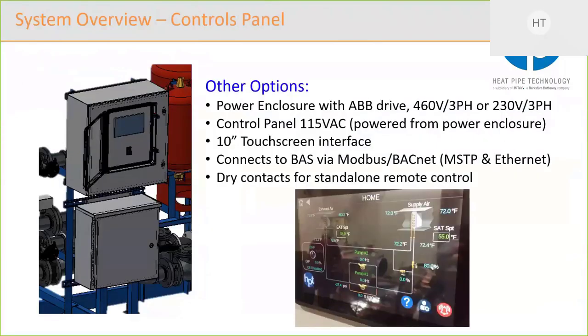So a quick look at the control panels. I mentioned before that the upper panel is the control panel, the lower panel is the power panel, and that includes the ABB drive. So we've designed for 460 volt applications and 230 volt applications. For those in Canada that might be using 575, we're very capable of doing that. We haven't pre-engineered that yet, but that's just around the corner. The control panel itself runs off 115 volts, but you don't need to worry about that because that is coming from the power enclosure. You just have to provide your 460 or 230 or 575.